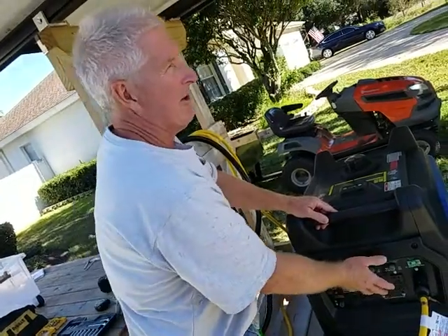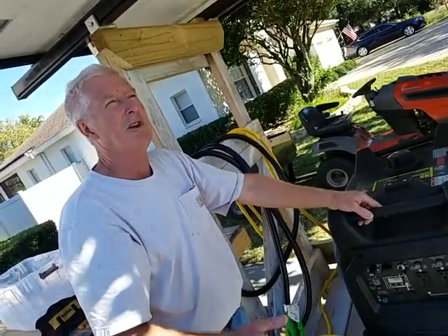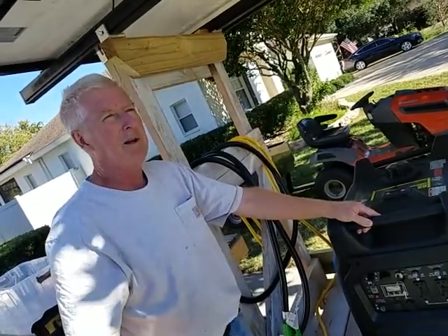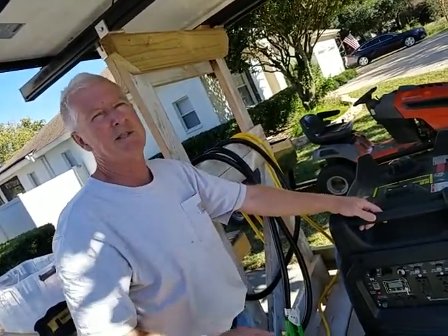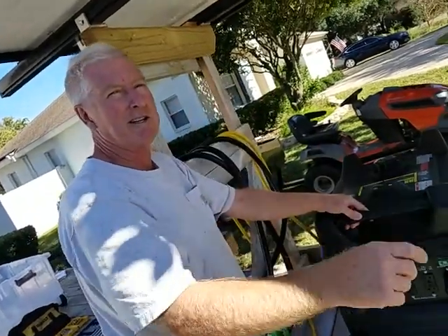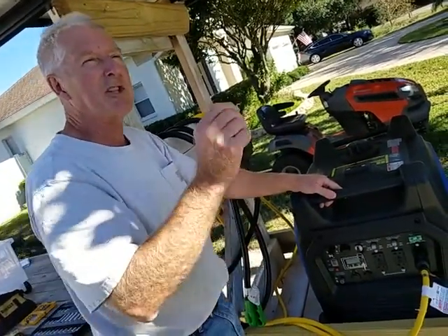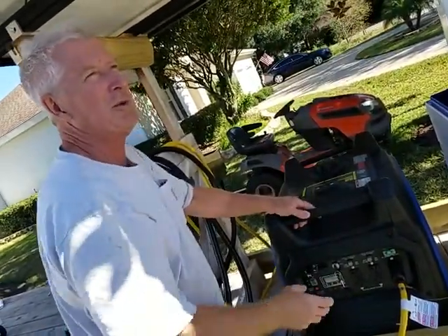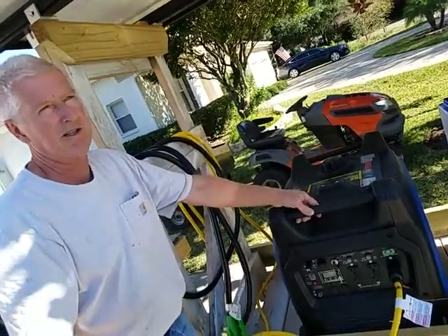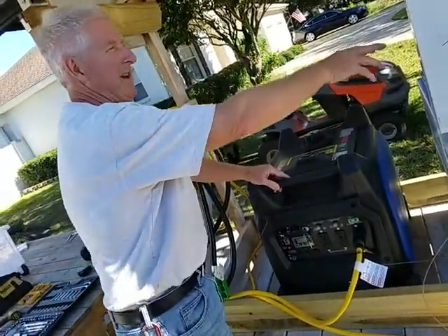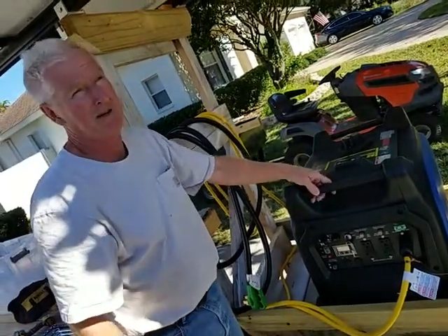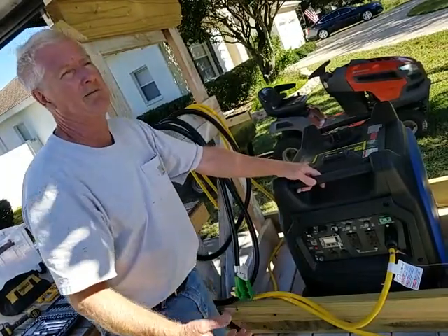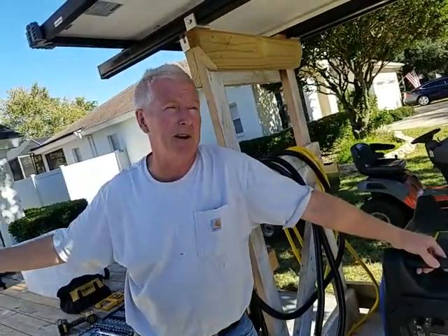So the generator is going to have logic in it that's going to say, you can attempt to start me for this many seconds on one attempt. And then it would have a pause. And then it would say, we're going to give you this many seconds on the second attempt. And then it may even shut you out so that you don't get a fifth and a sixth and a seventh attempt, because you wouldn't want to do that. Something's wrong, right? And then the inverter has to have sufficient intelligence to say, stop trying. That intelligence you're not going to get in my little Honda 3000 EU generator that's sitting in my garage.